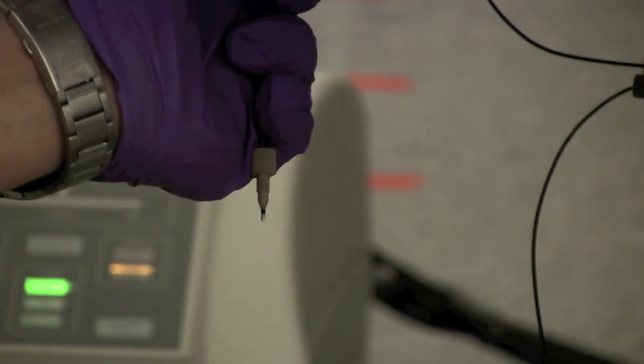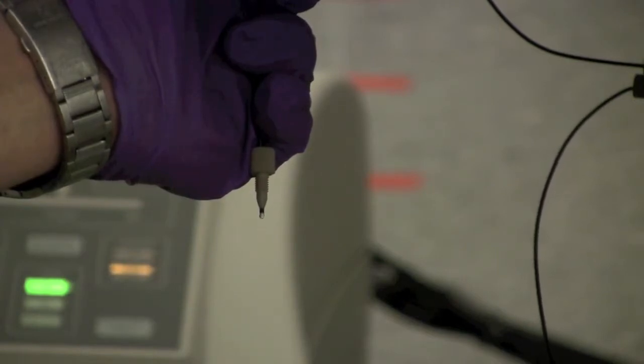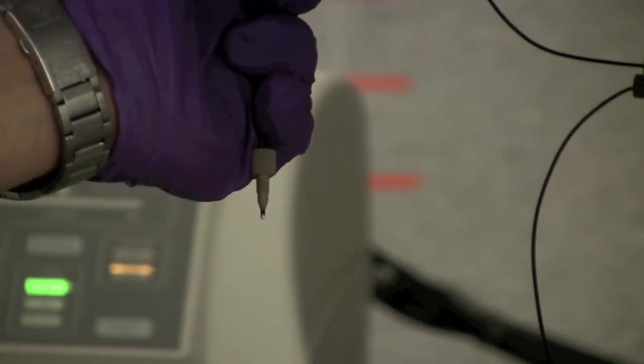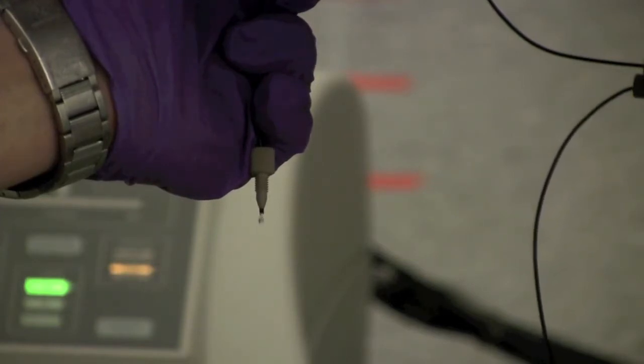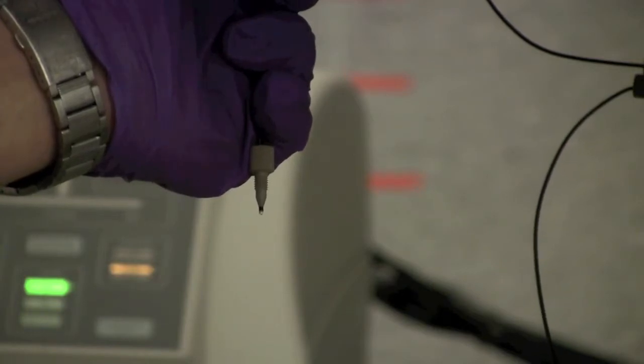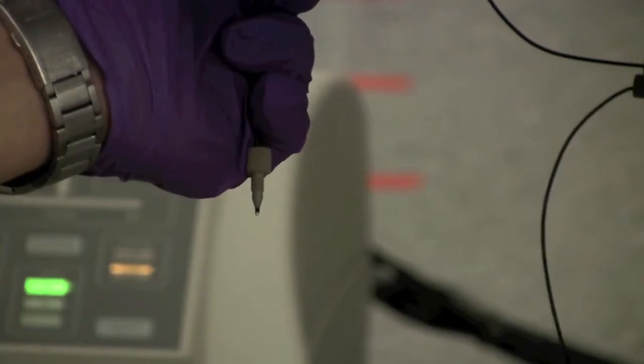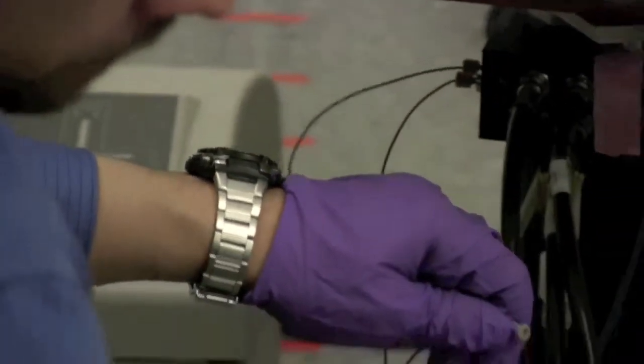In this case, things are flowing well, so we're going ahead and finishing out the flush with chloroform. Now, it may not be obvious, but it's a good idea to push the chloroform out again with air before we actually load our sample. The reason is we don't want to dilute whatever sample is in there, so if the probe is full of chloroform, it may dilute the sample somewhat. So I'm going to go ahead and use air again and push out the chloroform that I just flushed through the probe.